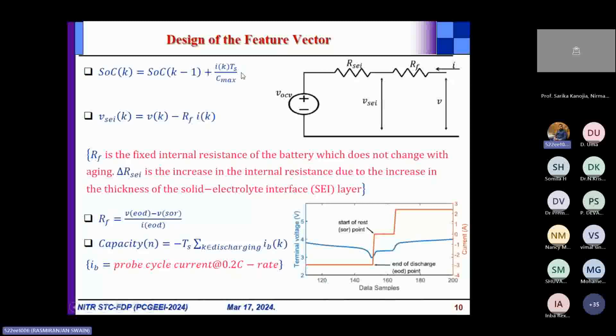Current times the sampling time, at whatever sampling rate it has been gathered, divided by C max, the maximum capacity. If you want to find the state of charge for the k+1th instant, that equals the state of charge at the kth instant plus this term. We need information of the previous SOC and the present value of the current, which gives the state of charge value of the present instant.